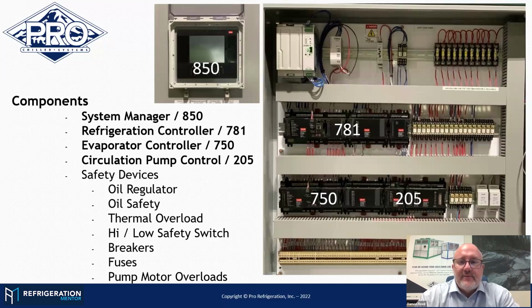So we utilize the Danfoss refrigeration control components. We use the system manager, which is up here in the top left. This is on the front of the electrical control screen. Kind of over my shoulder, you can see I've got a front end picture of a Pro Green unit. So on the one side, there's the 850 HMI. We have that in a completely watertight sealed enclosure cover, but it's clear plastic, so you could still see the HMI face. That's talking internally into the control system with the refrigeration controller, which is the 781. It's talking with the evaporator controller, which is the 750. And it's talking with, it's our circulation pump controller, which is the 205. Those three are all talking together through a communication bus back to the system manager.